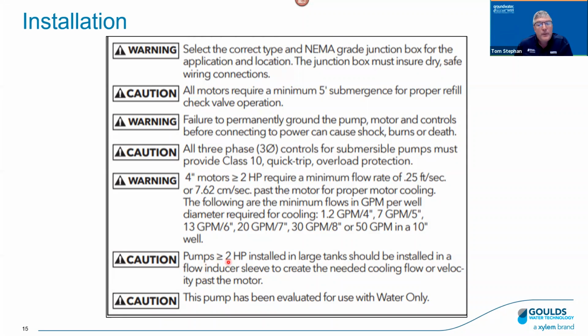The next one here, pumps greater than or equal to 2 horsepower installed in a large tank should be installed with a flow inducer sleeve. I have a picture of that, so we'll cover that. That just has to do with knowing that a submersible motor is cooled by water going past the motor. And that's what you normally get, right?